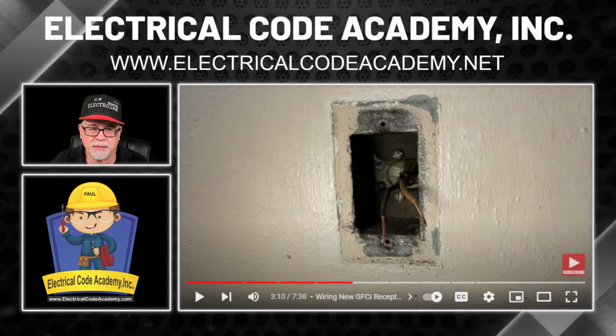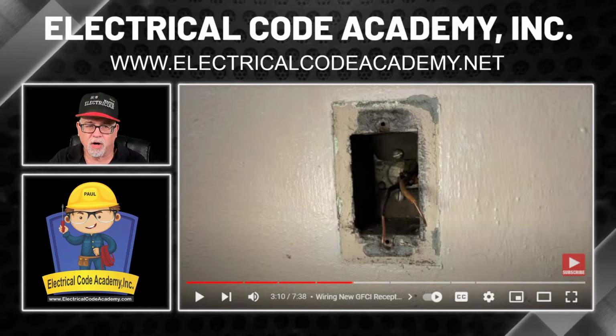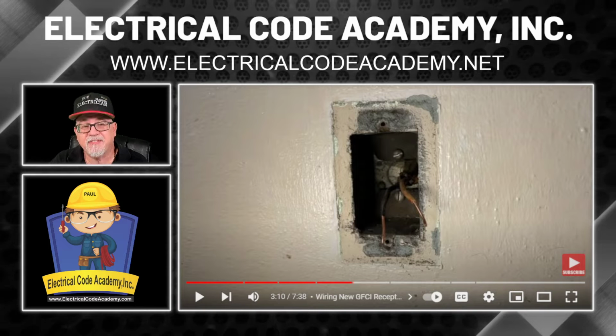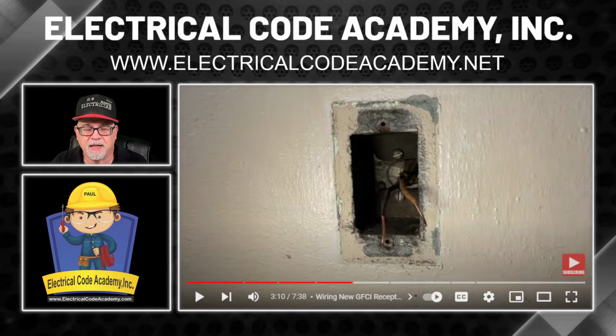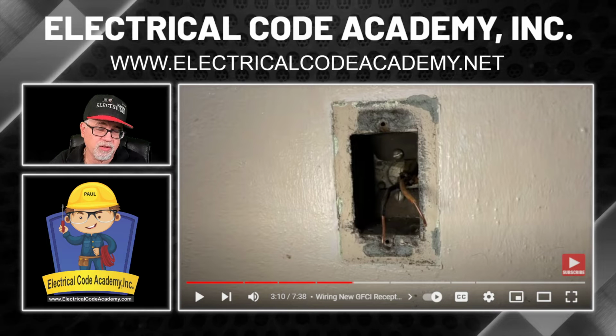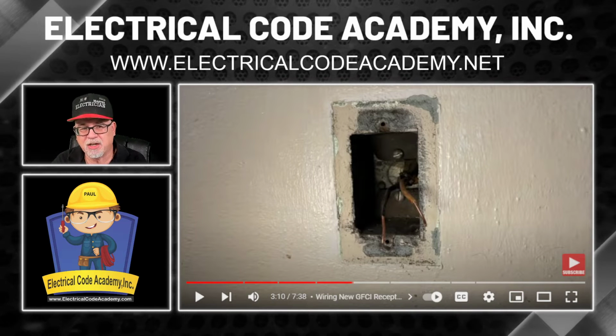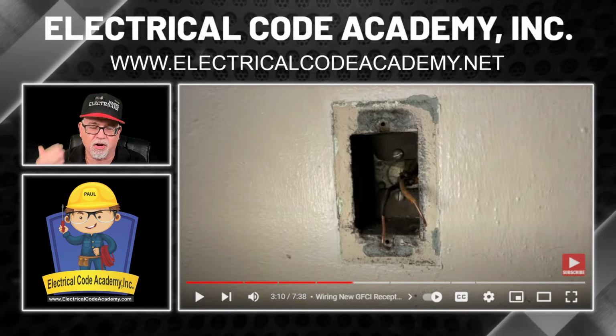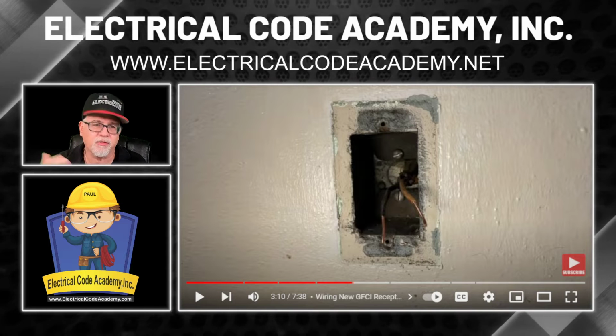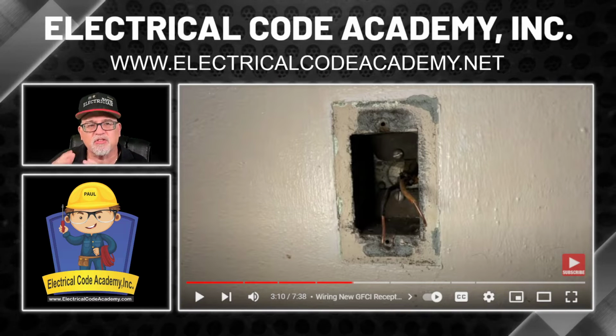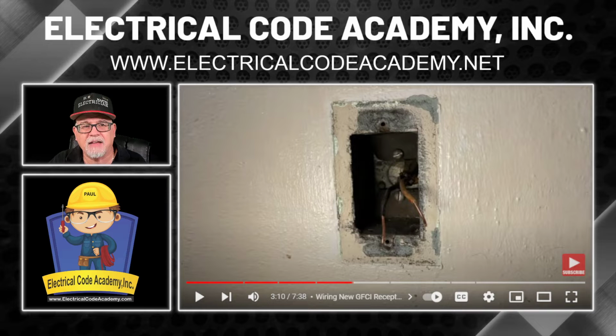That's the traditional MC. Now, they do make smart products, or like we say, advanced, enhanced type of MC, where the armor can be used as an equipment ground. And that typically goes up to 6 gauge and doesn't get any larger than that. So it's not the large feeder type MC that can get that smart ground. Or Southwire has one called MCAP.